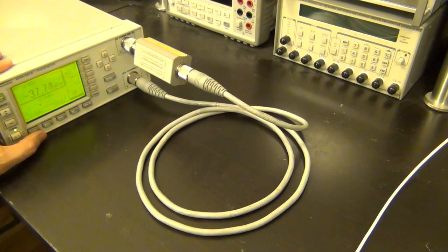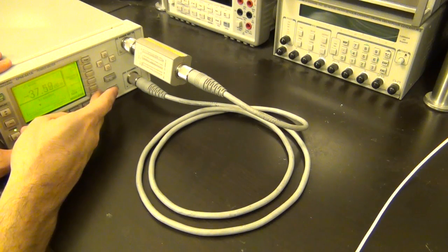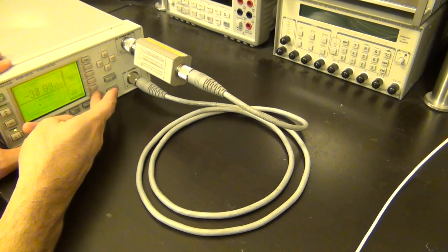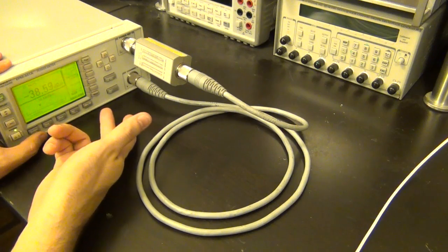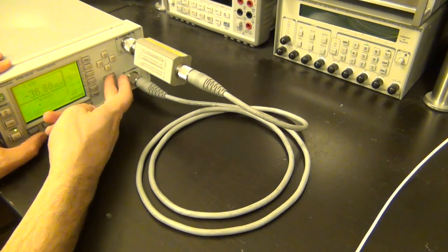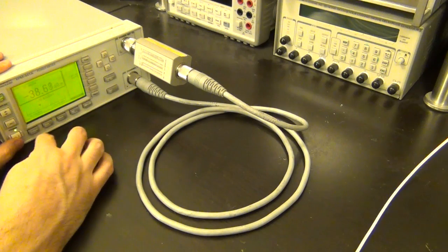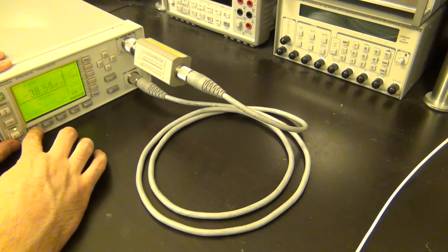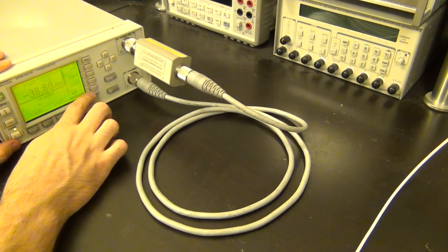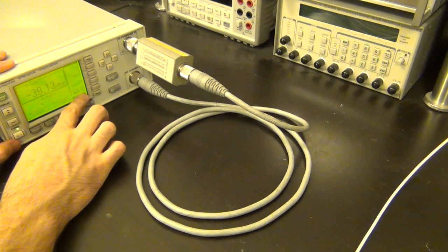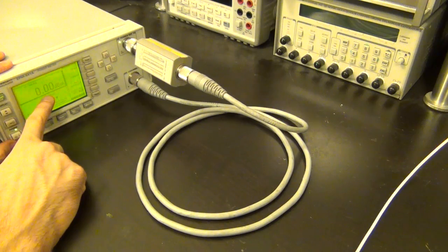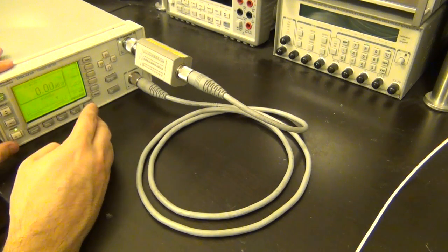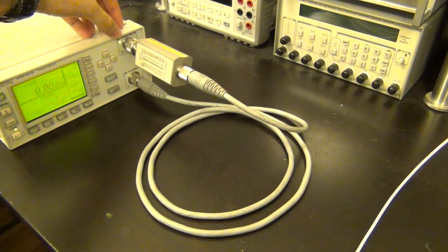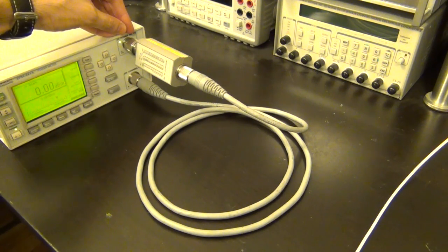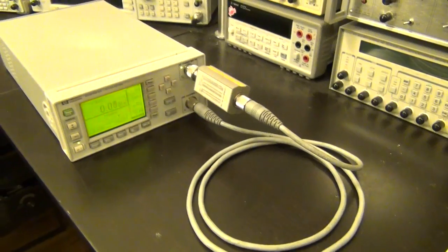That's annoying. If I go under system, if I go on second page, I should be able to turn the output on. How do I do that? Let's see. There is a way to actually force the output calibration to be turned on. There it is, power reference on. So I can turn the power reference on and off. If I turn the power reference on, now you can see it will say exactly 0. That doesn't mean it's correct because it's just comparing it versus its own calibrated power that it put out during the calibration procedure. So I hope you can see this, by the way. I assume that you could, but there you go.